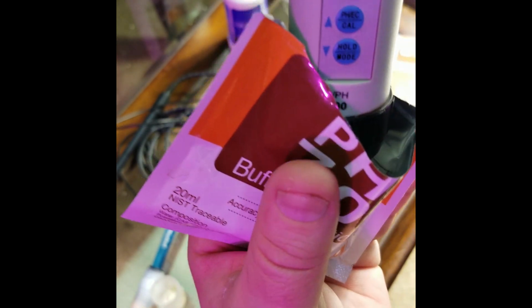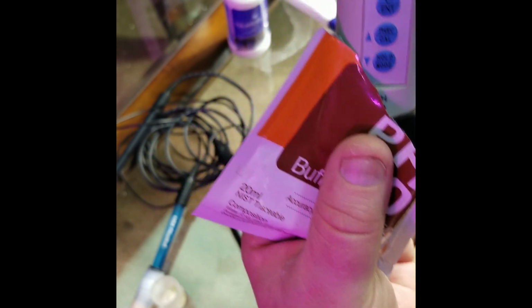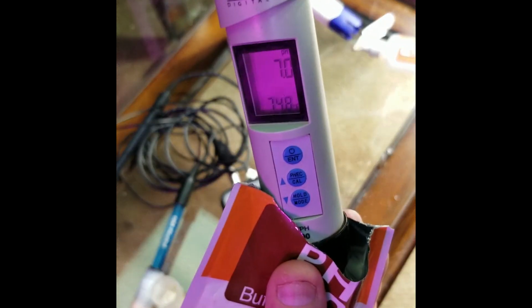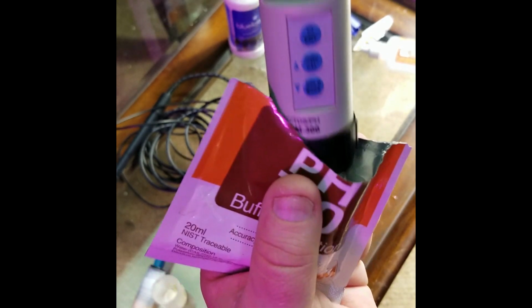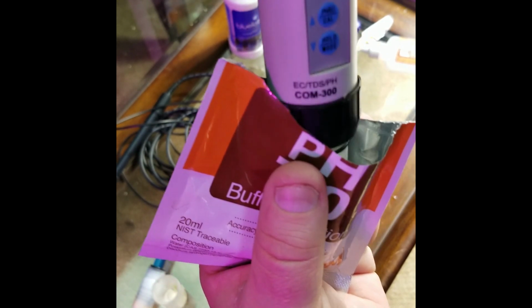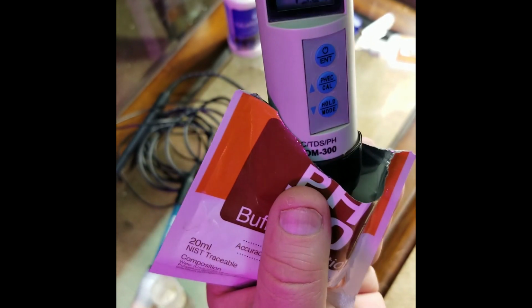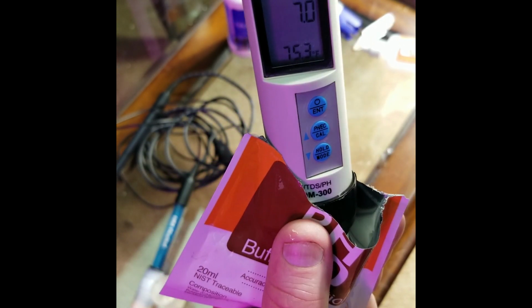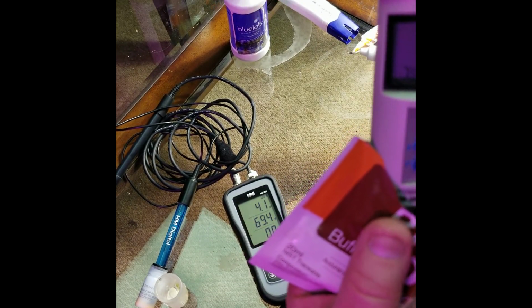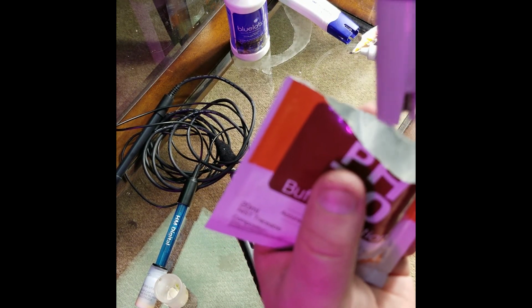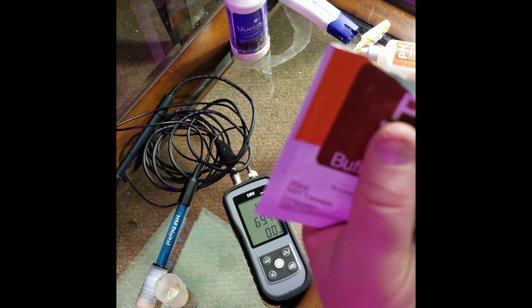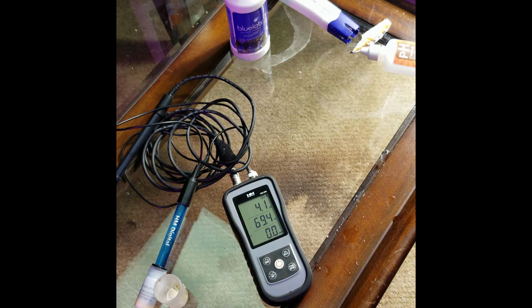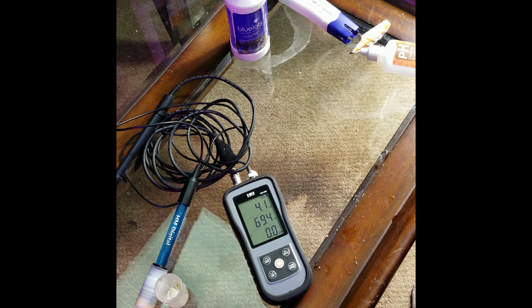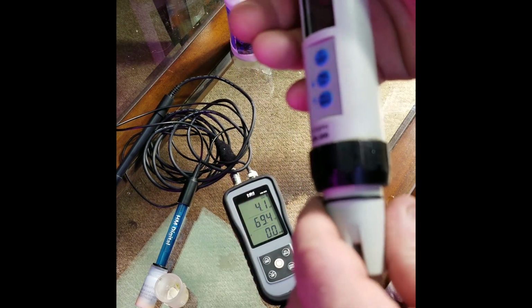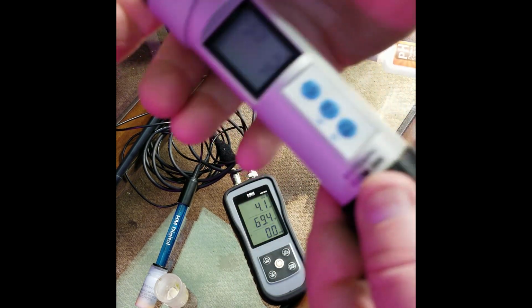Now you can always go back and do it, but every time you go back, putting some 7 into the 4, you can screw up the packet of 4. So I like to only do it just the one time. That's why I always do 7 first, so it's the most neutral and should have the least amount of effect on the 4 packet if more of this water gets in there. If it was alkaline, it would react. So the fact that it's neutral, and these are quite durable meters. Obviously, you don't want to bang around, but I shake the crap out of them and they stay running just fine.